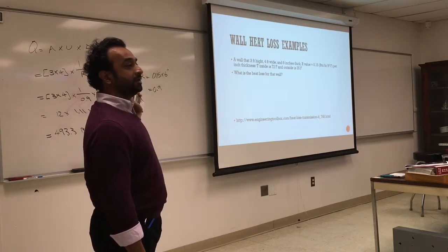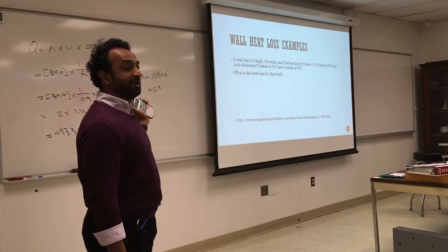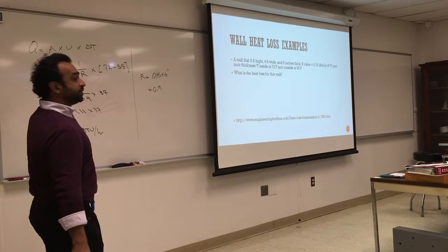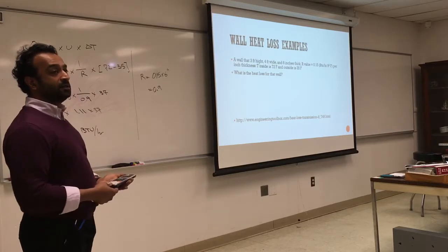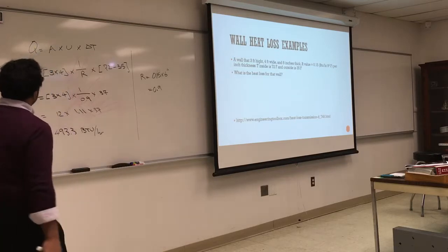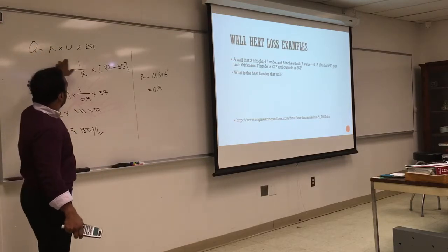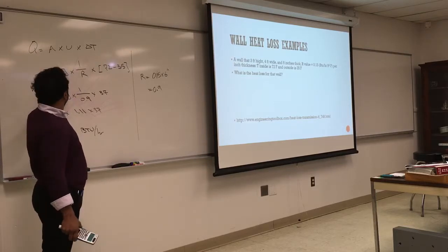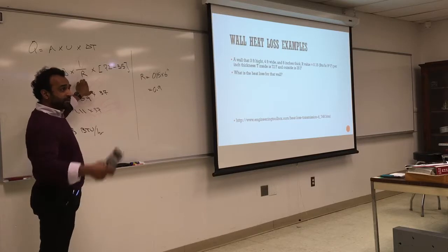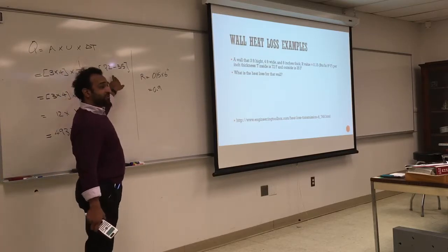Use a calculator. A lot of folks have an issue with not having enough patience to go step by step. They try to just chunk it down and put everything together in their head and just give me a number. The more you have patience and put it step by step, the better, because it will make sense to you. So this is the heat loss through a wall. You get the equation from the sheet. You put it down, then you fill in the blank. Area, U is 1/R. It's in the sheet. Temperature difference, high minus low.